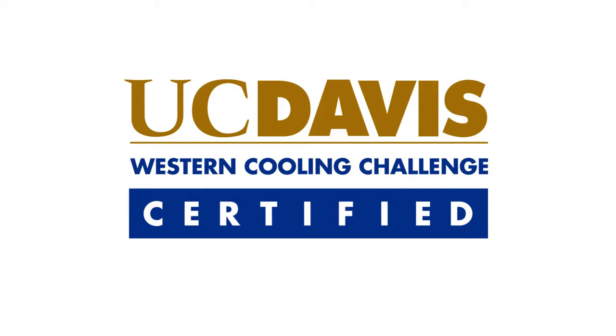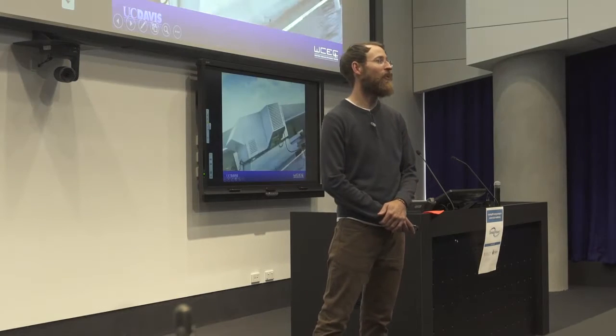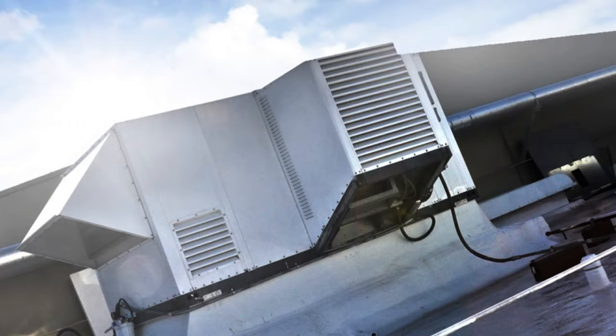So several years ago, we started a program we call the Western Cooling Challenge. We're working with our manufacturer partners, invited and challenged them to provide solutions that would meet this form factor and reduce peak demand from cooling by at least 40%. We've been working with a number of different technologies that have come into the fold to be evaluated by our program in the last several years. The first entry was this unit developed by an American company called Coolerado, which Seeley has very recently acquired. It's exciting to have that new partnership developing. This system we laboratory tested with the National Renewable Energy Lab, and then subsequently ran a number of field tests, and it showed about 65% energy reduction at peak.